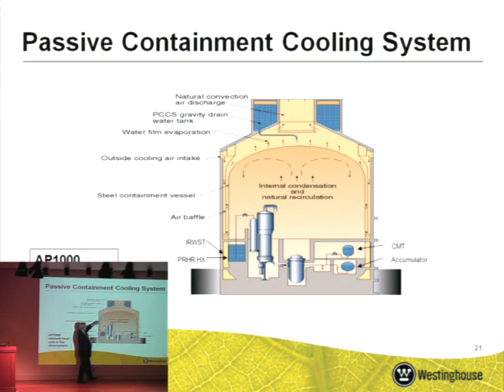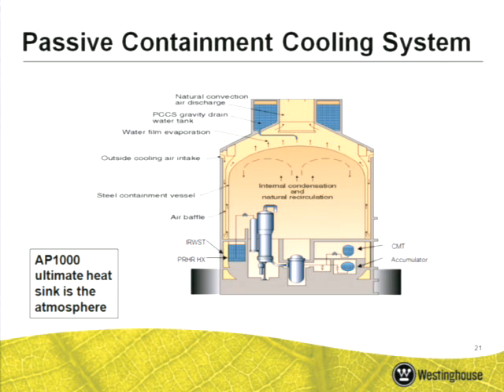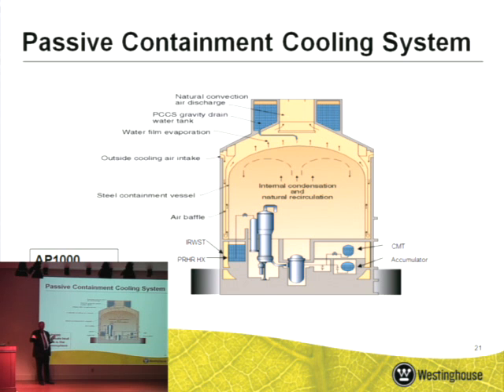So basically, the water comes down, and the tank is designed with standpipes so that you can have a high flow at the beginning. You really want the water flow to match the rate the core decay heat goes. So at the beginning you want 6% water, and at the end you want less than 1% water. With standpipes, as the level comes down, you get less flow, and below another standpipe you get even less flow. All done passively, so you can control the heat removal from the containment.